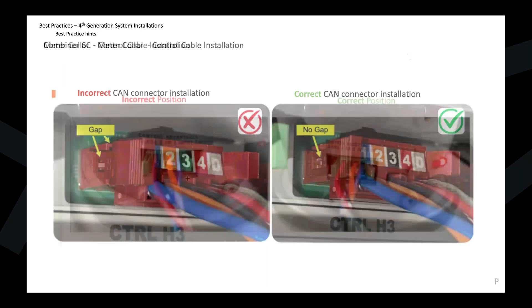And as John's showing here on the screen, same thing within the Combiner 6. We've seen those issues as well with the headers, not only on the meter collar one, which we're showing here in red, but also on the green ones for the batteries. We can have that alignment off just a little bit. And on the picture on the left, you can see that there is a gap where that connector was pushed into the header and it was off. You didn't make good contact. The one on the right is fully secure. You can see the locks tucked in there. And again, if you do a tug test, it won't pull out.